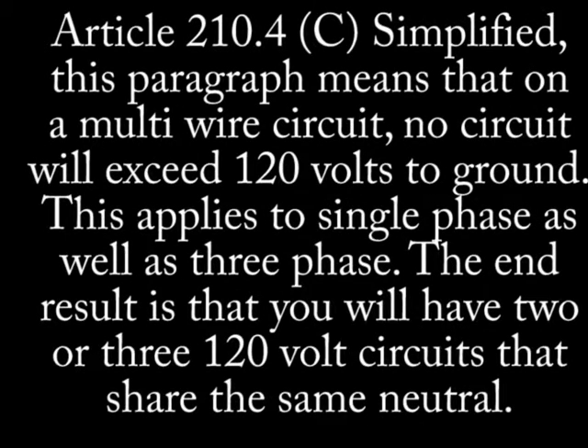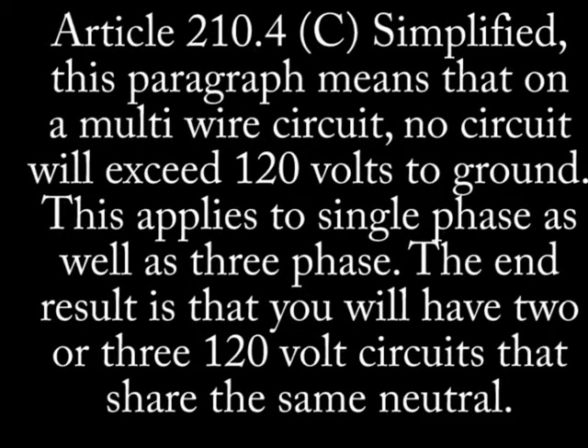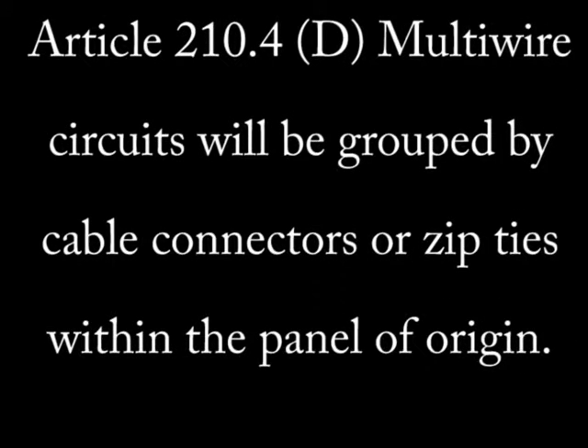Article 210.4 section C. Simplified, this means that a multi-wire circuit is not the same as a two-pole 240-volt circuit or a three-wire circuit exceeding 120 volts. It strictly applies to independent 120-volt circuits that use a common grounded conductor or neutral to complete two or more 120-volt circuits.